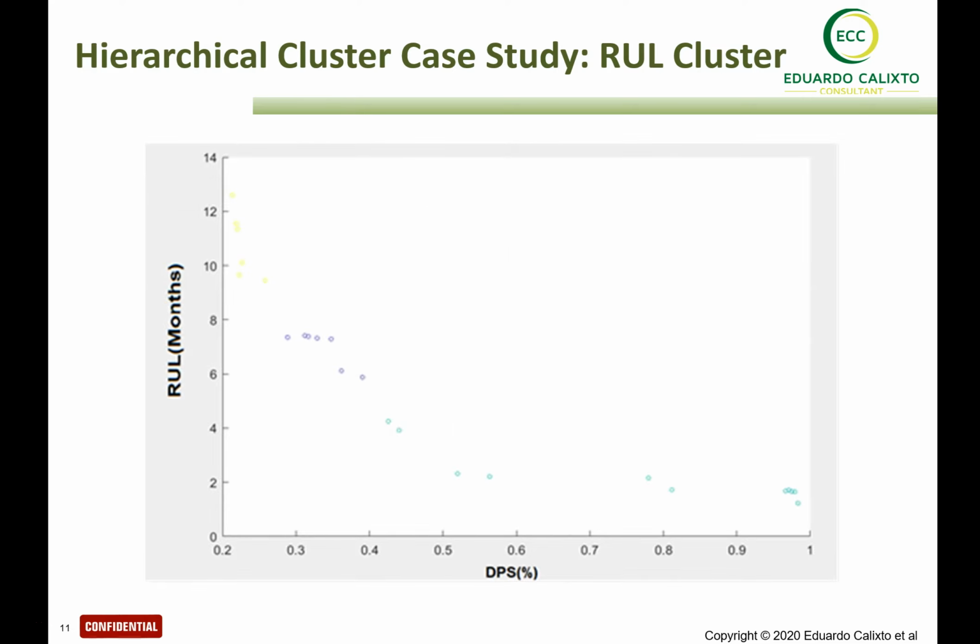By applying this methodology, the clustering based on hierarchical clustering, as I already demonstrated, we will have 1, 2, 3, and 4 clusters. So there are 4 groups of fan bearings from the heat exchangers that we are putting together. You see that we organize our preventive maintenance in these 2 groups. This one is the most critical one. We can even have 2 other clusters here.